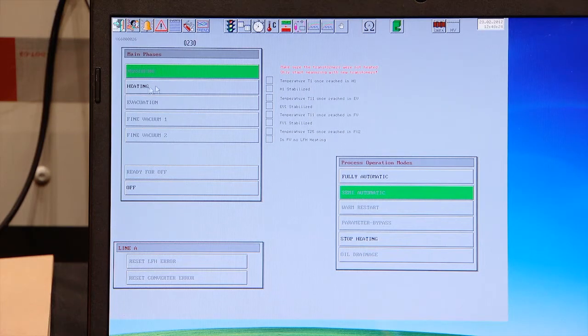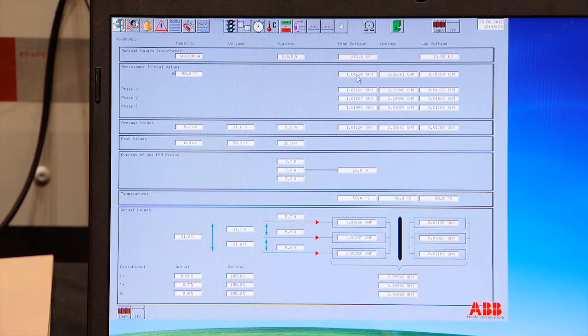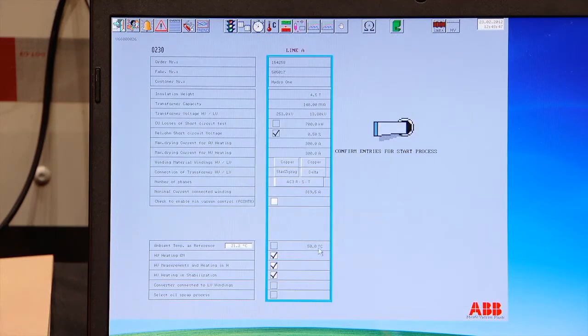So we check our values. We have now the resistance measurement on the high voltage. We have it for the low voltage. We have also the measured average resistance. This is now set to our initial temperature, and that's what's so important to check, that this is 50 degrees, is what we put on the hand page as 50 degrees down here.